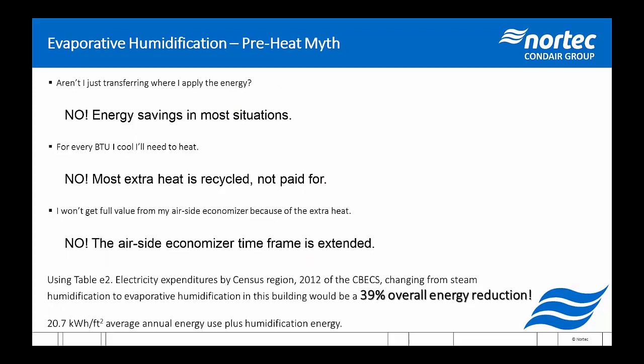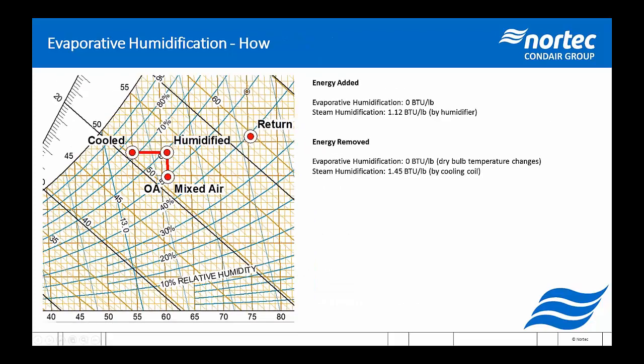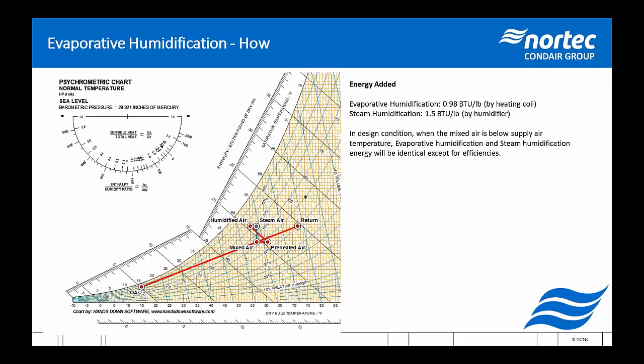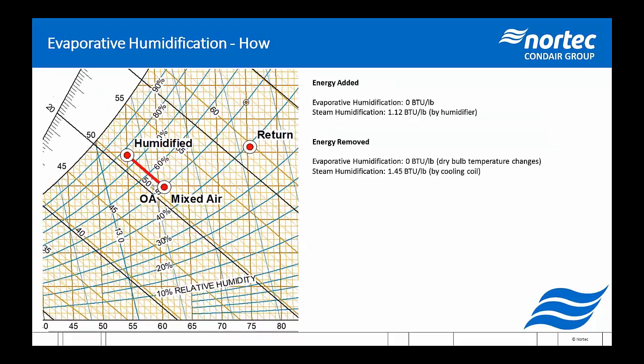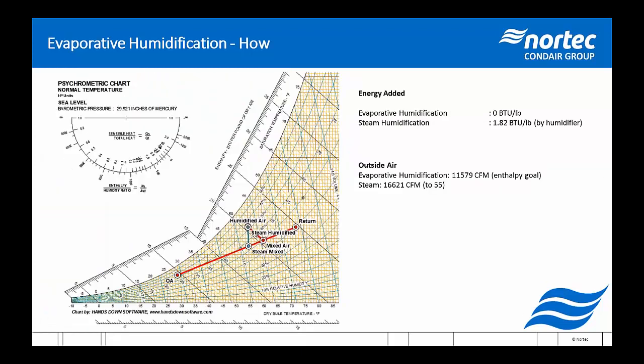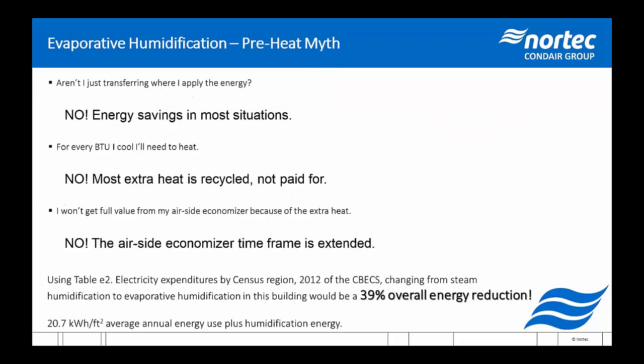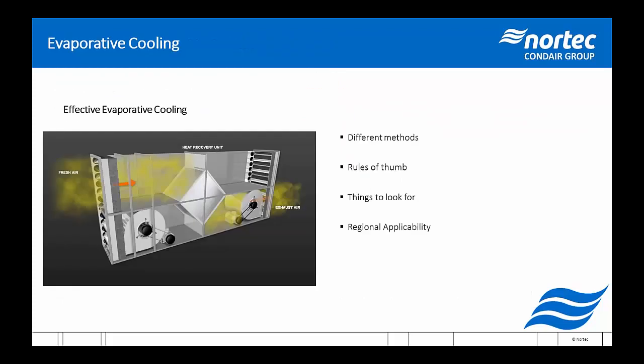So let's go back to our preheat myths. Aren't I just transferring where I apply the energy? Not necessarily. Again, if we go back to the design condition slide, in this case, yes, that is what you're doing. You are transferring where you apply your energy. But in the other 95% of the year that you're humidifying, you will find some energy savings by evaporative humidification over steam humidification. Whoop, overshooting.